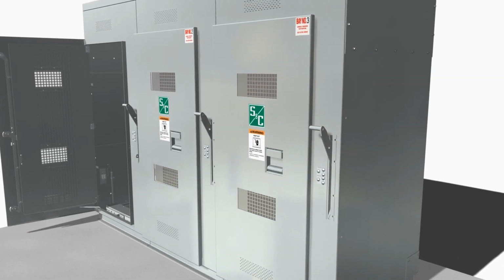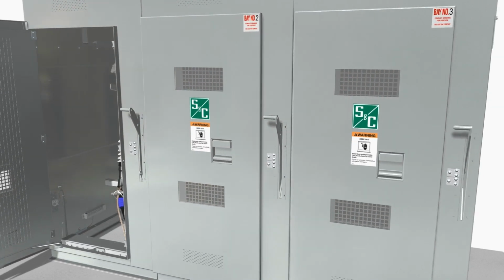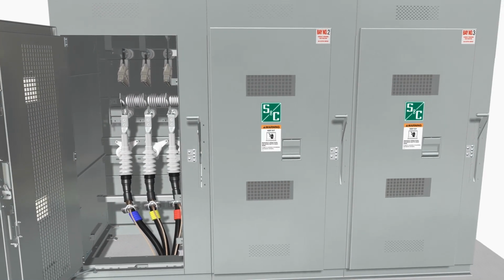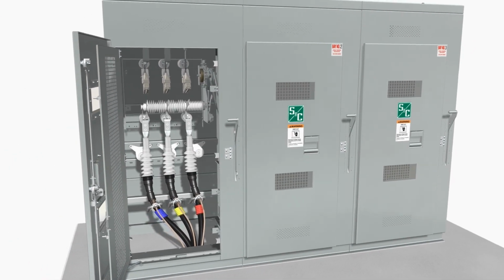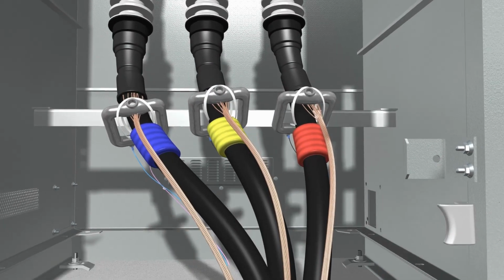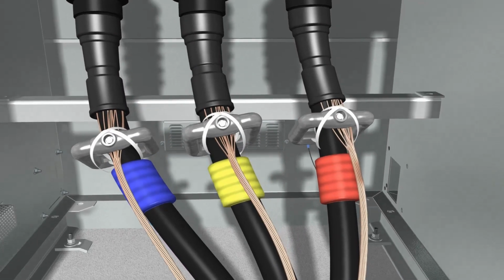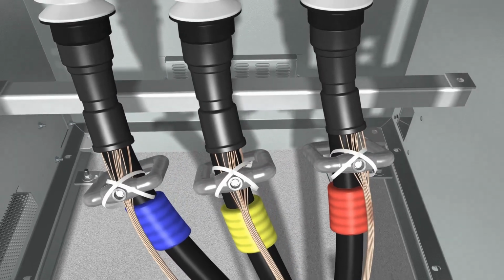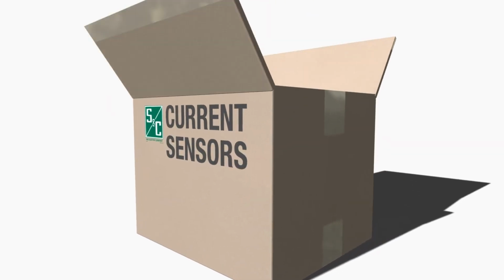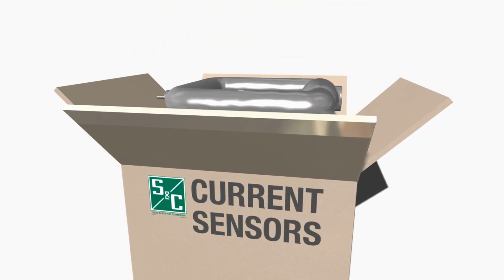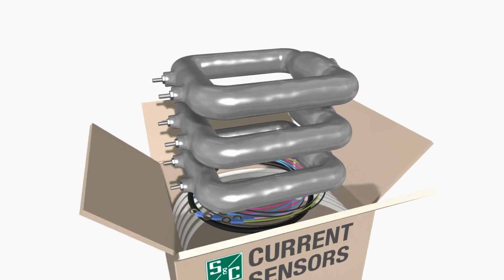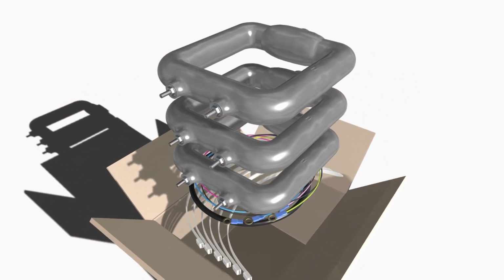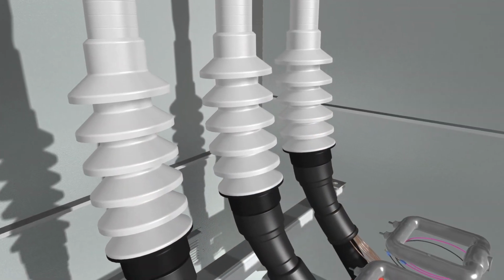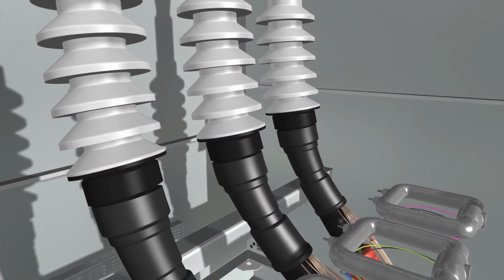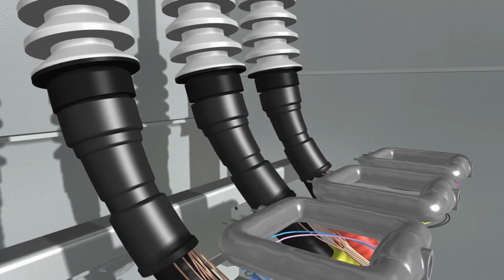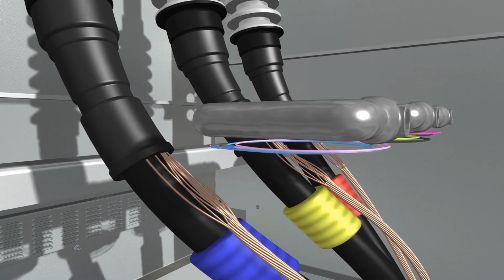Step 18. Switchgear may be equipped with S&C closed gap current sensors, which can be used with the optional overcurrent lockout feature furnished with the Micro AT source transfer control and with the optional Type ZSD overcurrent relay. These sensors are packed separately along with a supply of plastic tie wraps, connectors, and hardware. The control wire leads to be connected to the current sensors are coiled and taped to the interior side wall of the appropriate enclosure.